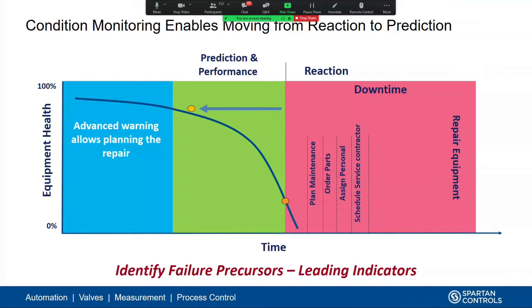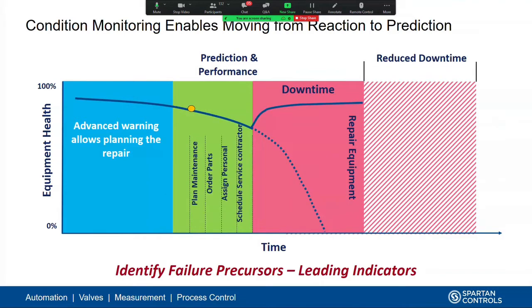So with this type of technology, we can detect that fault condition online, and as you see here, we can move all those planning activities much further ahead. Instead of waiting for that asset to fail, we can get all the parts organized, we can get the tradespeople organized, we can coordinate with operations of when a good time would be for us to take that pump down so we can actually do the repair. And then at some point we have to physically shut that pump off and do the repair. So there's always going to be that downtime associated with the repair. We can't get around that. But what we can do is move all those planning activities further ahead in the cycle so that we're doing those while the asset is still running, therefore minimizing the entire downtime associated with that failure.